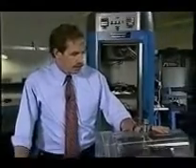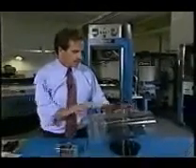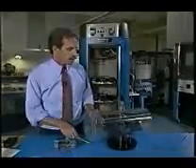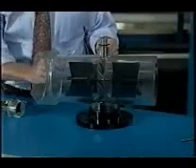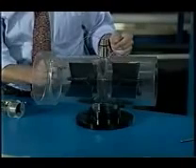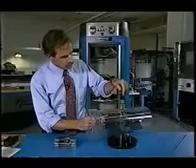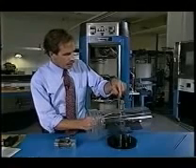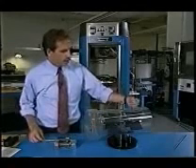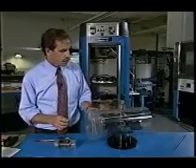I have here some examples of some rotary flow meters. This is a very large flow meter that's designed for use in large pipes with liquids. And what happens is, as the fluid flows down the pipe, it spins this little propeller in here. And as the blades of the propeller go by a Hall effect sensor, or it could be an optical pickup, it creates a pulse. And what you do is you actually calibrate the flow rate to the number of pulses coming through the system. Now, this one's designed for use with liquid.